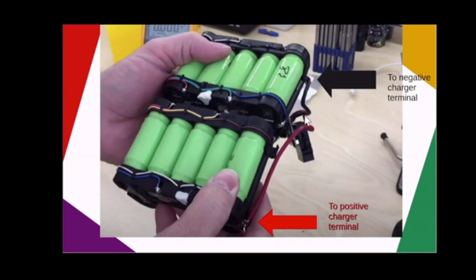and you have to watch it very closely and carefully. Don't leave, and watch the charge go up to about 50 to 52 volts and then take it off the charger. You have to watch it from beginning to end because it is directly charging the batteries, and that charge will not stop until you stop it. You have to stop it before these batteries overheat and catch fire. Another thing you can do is connect a very well charged battery to these terminals, positive to positive, negative to negative. That way the charged battery will charge the discharged battery, hopefully to the point where it will turn on the BMS, the battery management system, again.